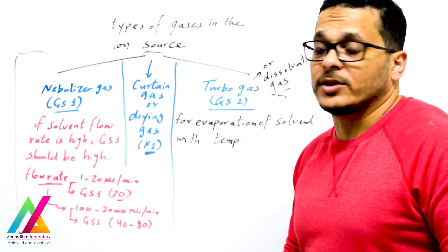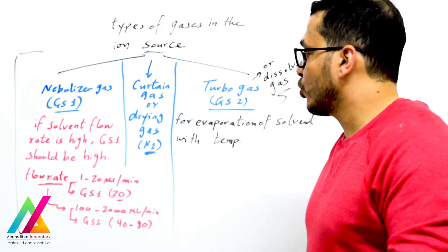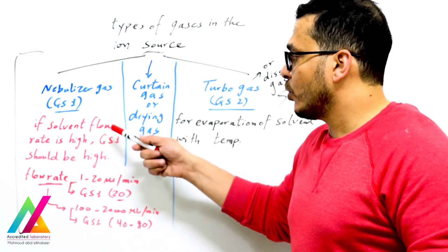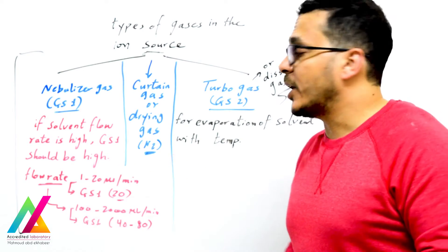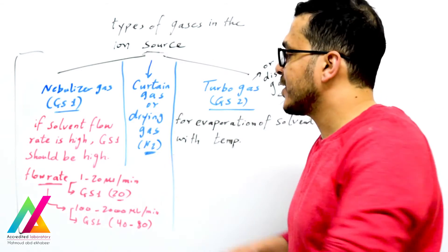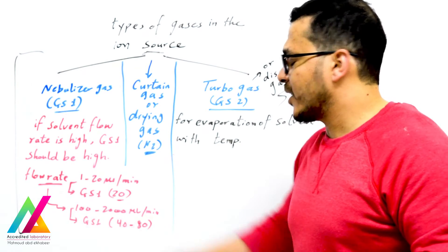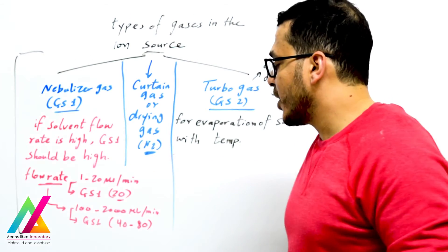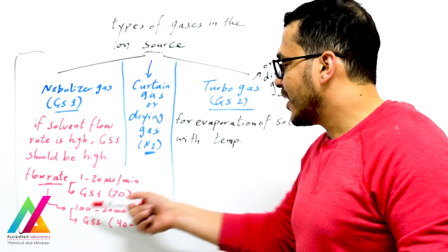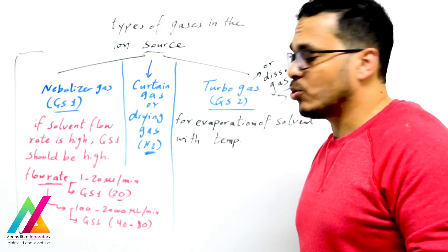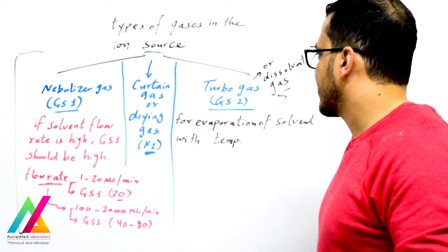Nebulizer gas (Gas 1) is used for nebulization of the eluent carrying sample molecules to form spray droplets. If solvent flow rate is high, Gas 1 should also be high. For a flow rate of 1 to 20 microliters per minute, Gas 1 should be set to 20; from 100 to 2000 microliters per minute, Gas 1 should be set from 40 up to 80, and you will optimize this accordingly.